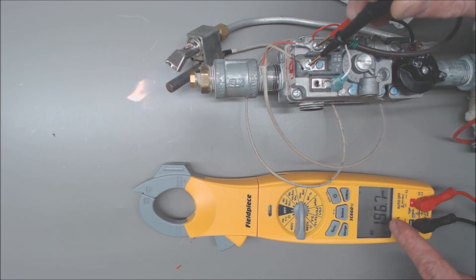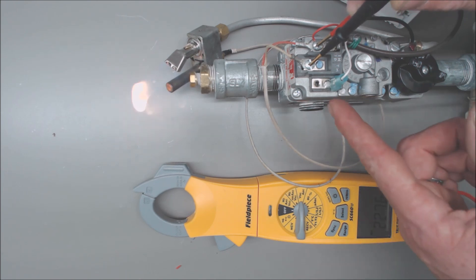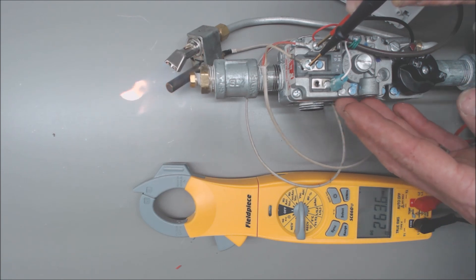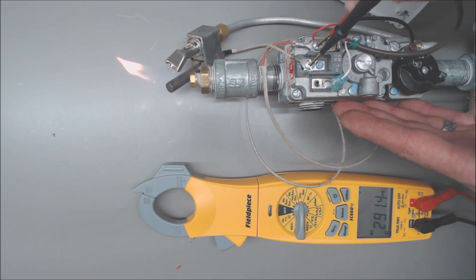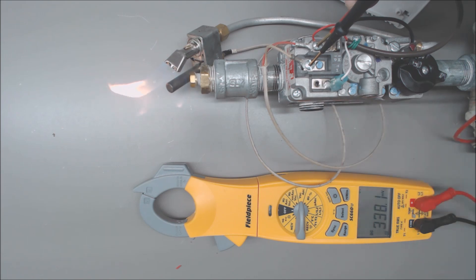You want to wait for your millivolts DC reading to get up towards 600 millivolts before you try to put a load on it, meaning you're going to turn the heat on. Once that happens, the voltage is going to drop. You just want to make sure that you maintain a DC millivolt reading above 190 millivolts DC, and that will allow this millivolt gas valve to work properly.